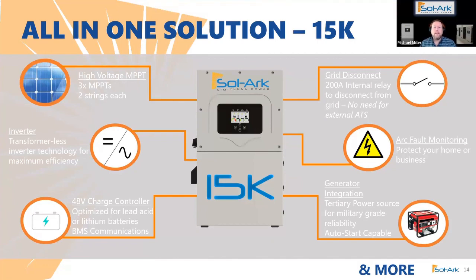So the Sol-Ark 15K here is the all-in-one solution. These are some of the key aspects. The high voltage power point trackers are built in. You have 3 of them. You can run strings all the way back to the inverter, and you have up to 6 total strings, two strings for each power point tracker. It's transformerless, so it's a lot lighter than the previous technology. It's not attached to a battery, so essentially it's lighter there as well. You have the internal 200 amp grid relay, 48 volt common platform, and BMS communications with closed loop communications with many of our partners. Arc fault monitoring, all that is built in. And then generator integration is a 2-wire start. Many generators can be converted to 2-wire start.